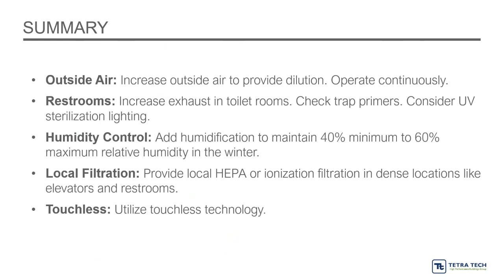In fact, prior to occupancy and after occupancy, we recommend the systems be run at least a couple of hours on the shoulders. For restrooms, increase bathroom exhaust, check the trap primers, and consider UV sterilization. For humidity control, add humidification where you can. Many buildings can't support it due to their facades, but 40 to 60% is the maximum level for health.